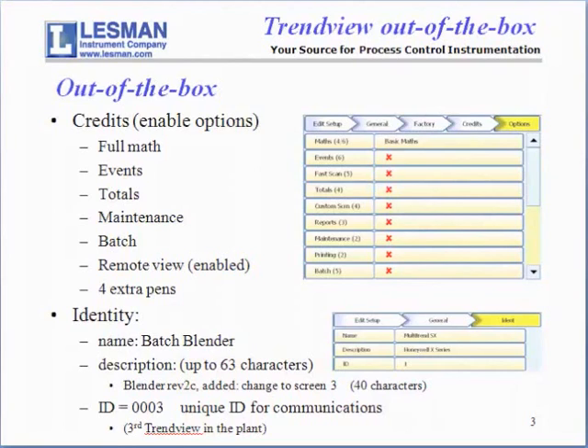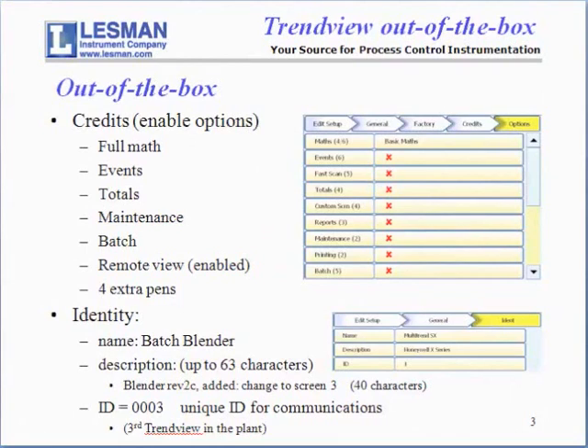Under identity, we're going to name the recorder Batch Blender, and then we're going to put a description in there. Best practice says this is where you put in the revision and the latest change you've made to it so that you can identify one setup change from another. And lastly, under identity, is the ID. We're going to call this recorder number three. It's a unique ID for digital communications, Ethernet communications, because it's the third TrendView in the plant.